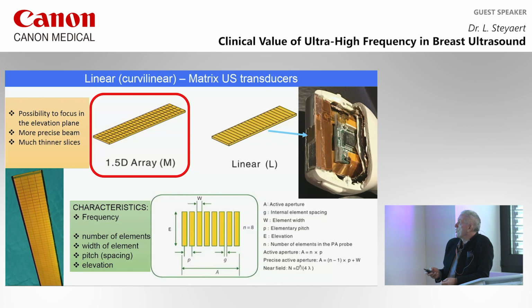If you take a transducer and slice it apart, you see the crystal elements. In the linear probe, it's an array with several crystals in one line, and depending on the characteristics, that affects your resolution. But with the new 1.5D or matrix transducers, you have several rows of crystals that make it possible to focalize in the elevation plane, that means in the plane perpendicular to the slice plane. And this gives you a much more precise beam and a much thinner slice thickness.